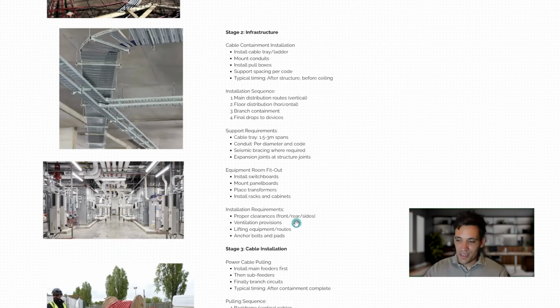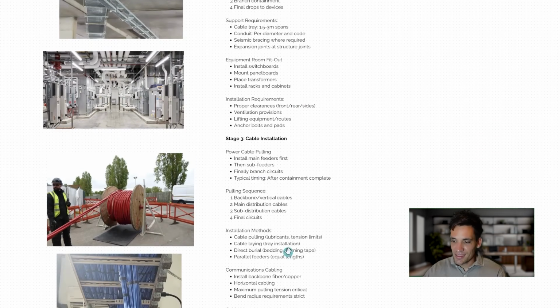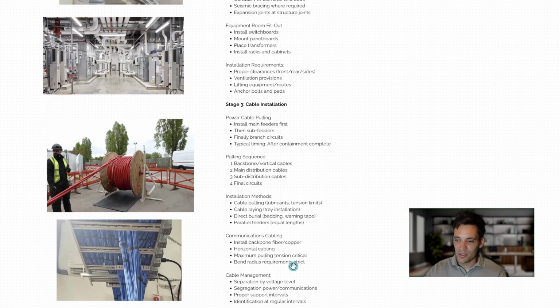Once all the cable tray's in and we've installed the devices, we can start our cable pulling. This is when we basically run out all of the main cables. Typically, we'll install the main feeder cables first, bigger cables, the sub feeders, and then any branch circuits we may do separately or we may do at the same time as we install the devices. Again, to do this, we use cable pulling equipment, so things like cable drums. We'll install the cables on drums, with cable pulling lubricant.